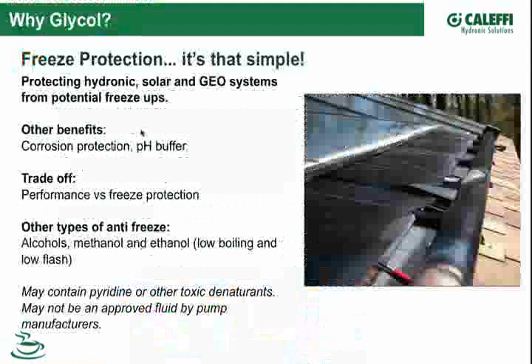The bottom line in our industry is that typically freeze protection is what guys are buying glycol for, but it brings a lot of other good things along with it, like corrosion protection. If you're putting a system in with brand new copper pipe, steel pipe, or cast iron boilers, there are inhibitors and products that passivate that metal, protect it from additional corrosion, and buffer the pH. The trade-off is a bit of a performance hit as far as pumping power required, but if you look at all the pluses, that sometimes gets overlooked, and people just say they're putting it in to keep it from freezing.